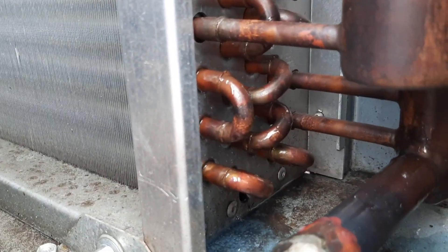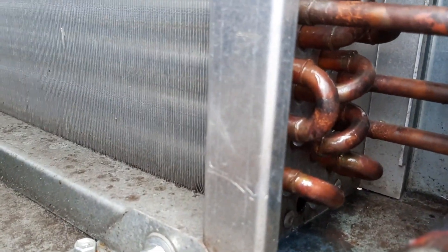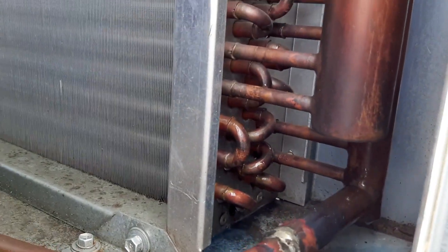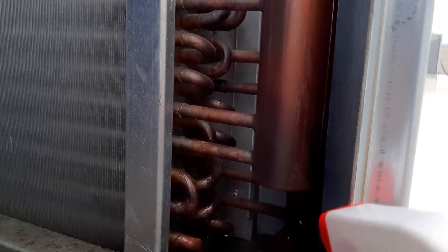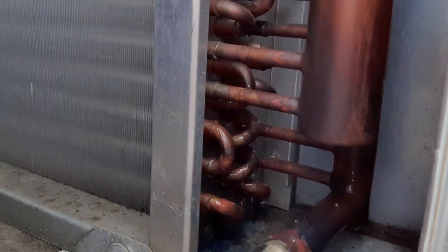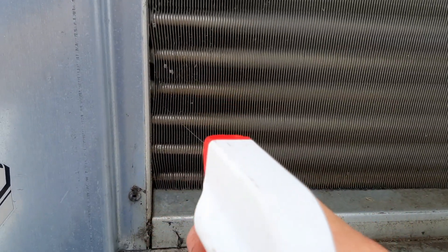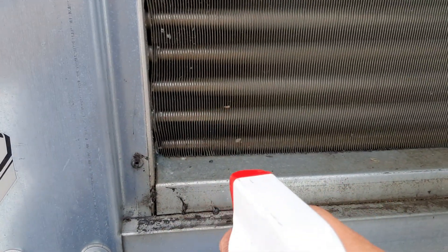Let that sit for a few and see if we get any bubbles out of it. Both my compressors have cycled off at this point. I don't see any other alarms so it looks like it's satisfied. Let's move over here — there goes one of my compressors starting back up.